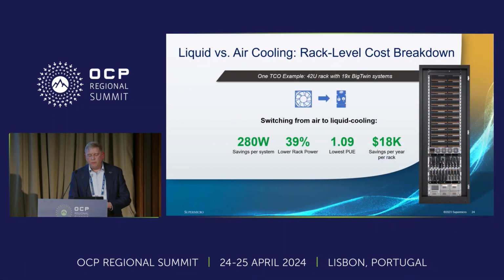So what can you expect? We ran a TCO model, which we do often for customers to help them estimate what they might see. In this case, we took an air-cooled system and a direct-to-chip liquid-cooled system and made them as similar as possible. We ended up with 280 watts in savings and 39% lower rack power. PUE dropped to 1.09, achieving $18,000 in savings per year per rack, which is impressive given current lower power rates in the States.